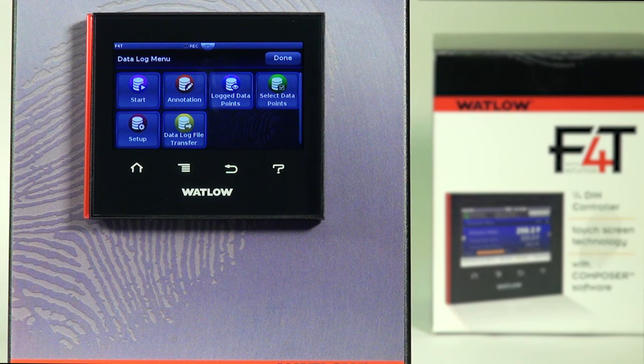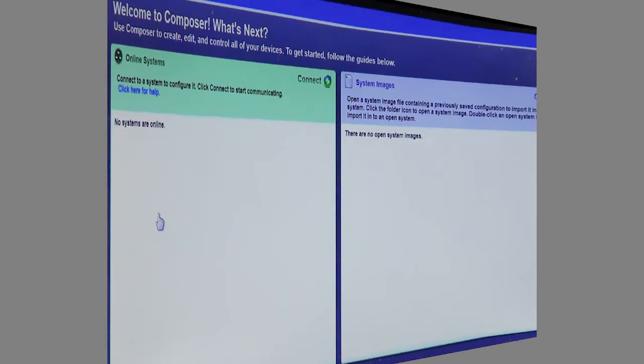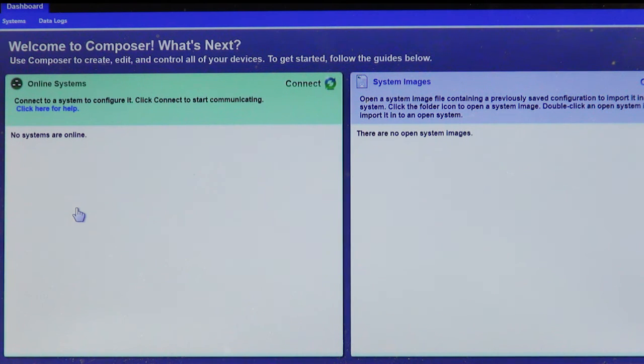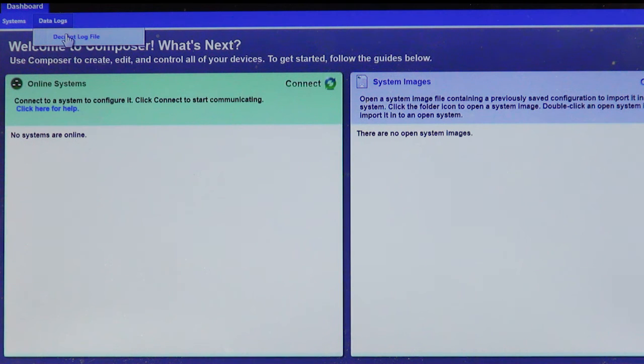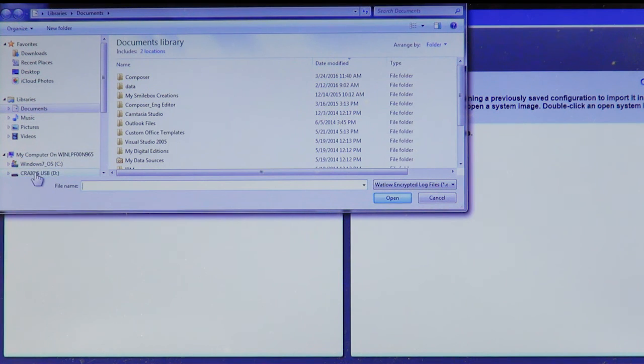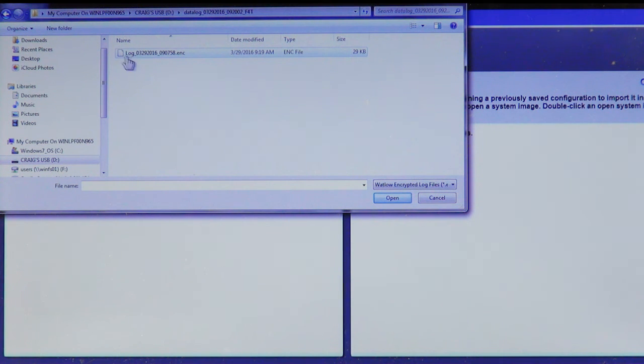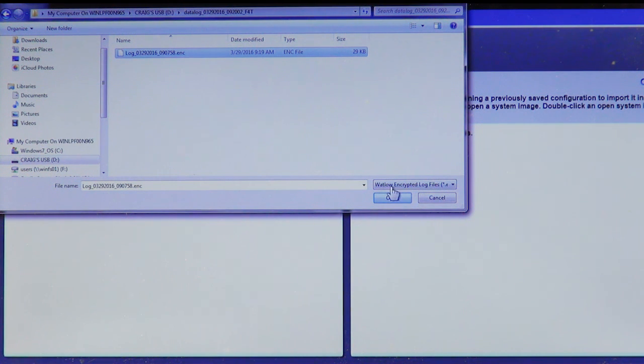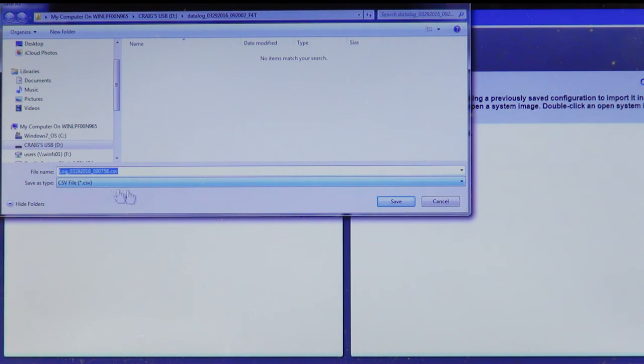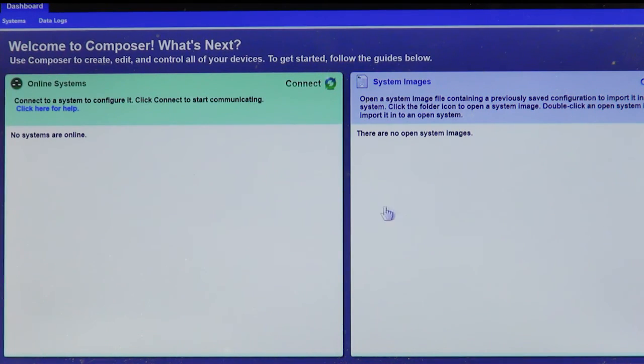If you created an encrypted data log file, you can use Watlow Composer PC software to create a decrypted file. Composer is free software available from the Watlow website. Click on the dashboard, then 'Data Logs,' then 'Decrypt Log File.' I've transferred the data log from internal memory onto a memory stick plugged into my PC. Navigate to your USB drive, find your data log records folder, and select the encrypted file — named 'log' followed by date and time stamp. Composer then creates a CSV version replica of that encrypted file. Hit save.